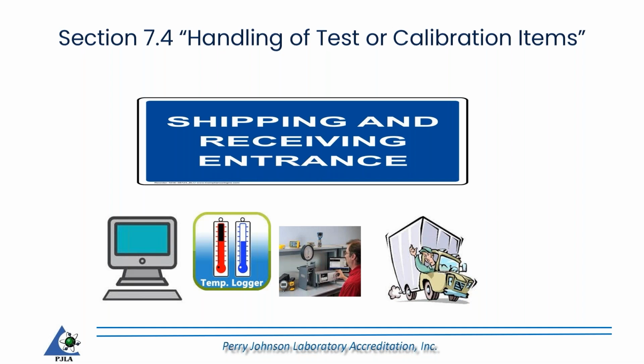We're going to start with section 7.4, which is the handling of test or calibration items. Sometimes I like to refer to this as the front door to back door. This is an area where items come into your lab, calibration items, testing samples. They're received, they're inspected, any deviations are noted. They may have to be stored prior to being tested or calibrated. There might be requirements as far as conditions that need to be met. Then the actual testing and calibration will be undertaken. And then lastly, return of the artifacts or samples, or disposal of the sample, are all items that this would capture.